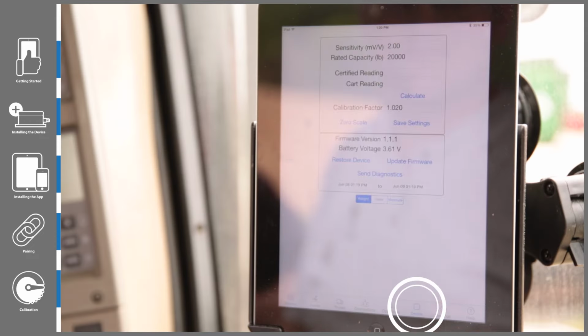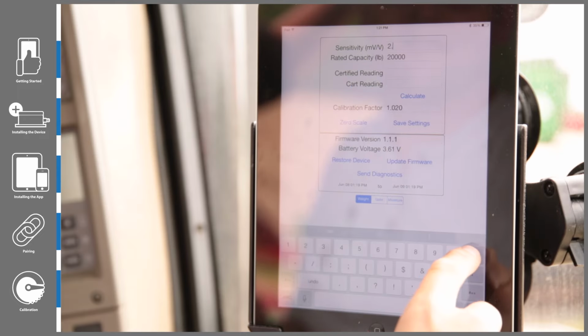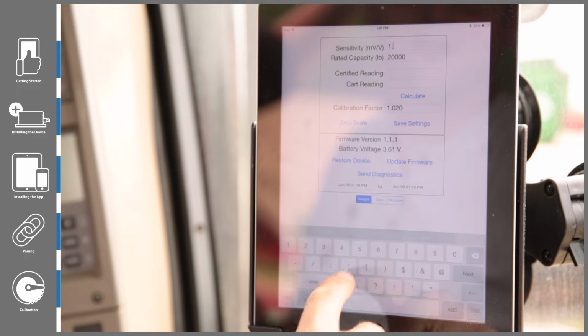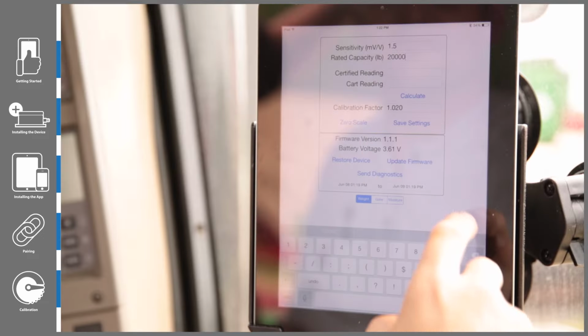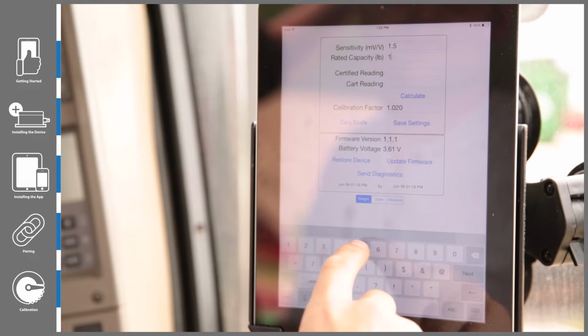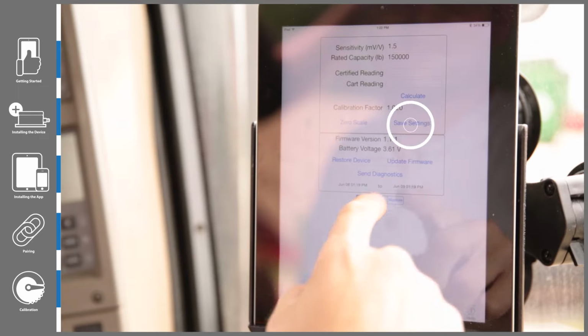Now press the device icon on the bottom of the screen. The sensitivity of the largest load cell is 1.5 millivolt per volt. Input 1.5 into the sensitivity field. Each bar is rated at 30,000 pounds. Multiply 30,000 by 5 because we have 5 load cells. We have a total rated capacity of 150,000 pounds. Input 150,000 into the rated capacity. Press Save Settings to save this information to the IFarm device.